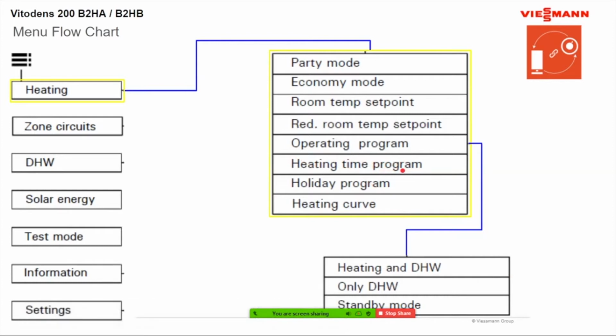Heating time program. So if you click on that, that's where you would go to your heat time program. And with the original boiler, you actually had to go in there and take the heat time program out because it was set up from, I think it was 600 to 1200 hours. So that means that boiler would shut down after 12 a.m. and it wouldn't come back on until 6 a.m. if you were running a room temperature set point. So you had to go in there and put it into a 24-hour time clock.